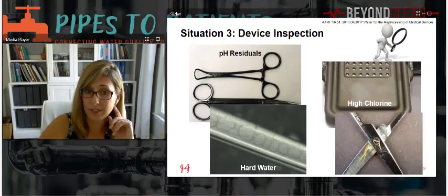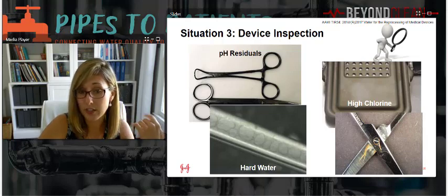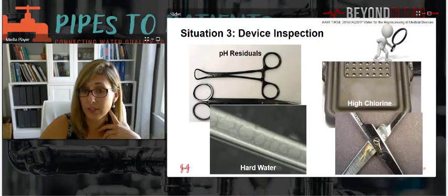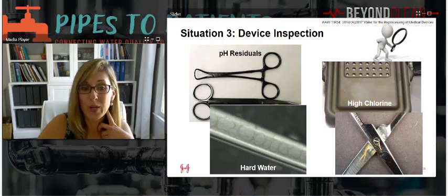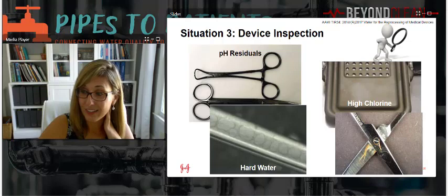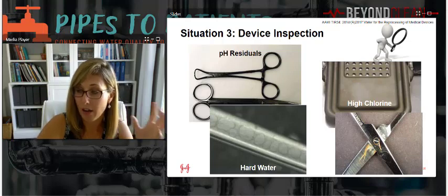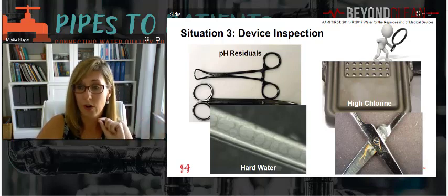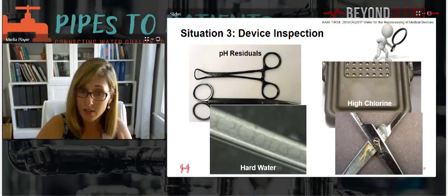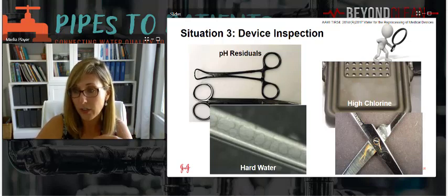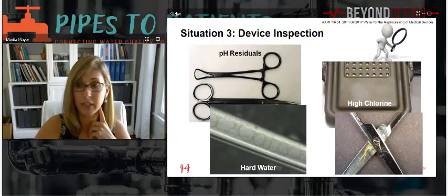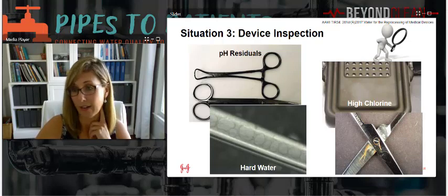And what about this one? It looks like a device that has some corrosion, some pitting, rusting, and it can happen when it's exposed to, again, chlorinated water or high or low pH. It also happens when saline is used as part of the point of use treatment. So if you are communicating with your OR staff and they're using saline water as a point of use treatment, please ask them to stop. It is really not good for the instruments at all.